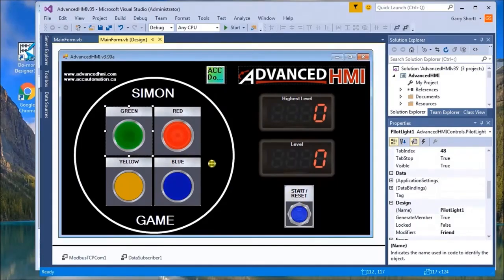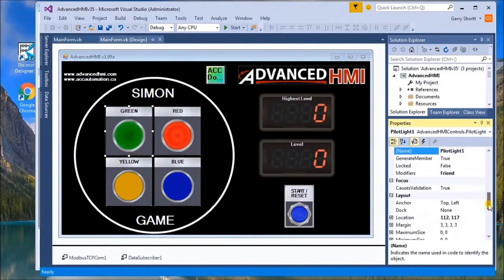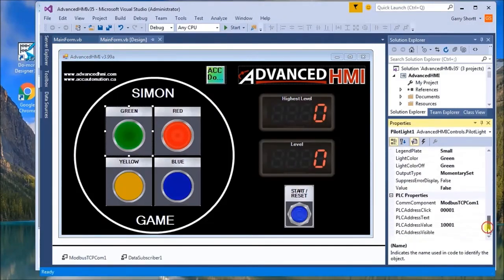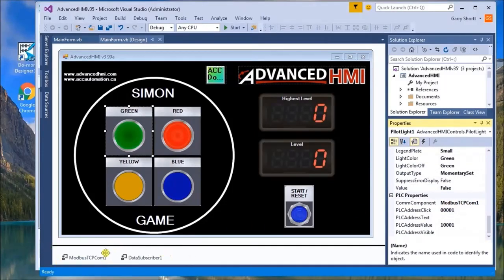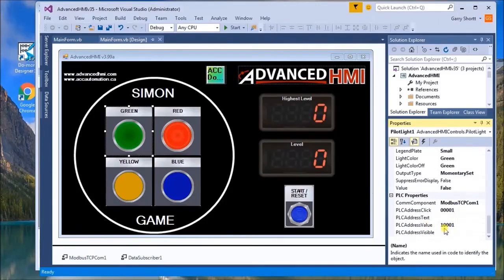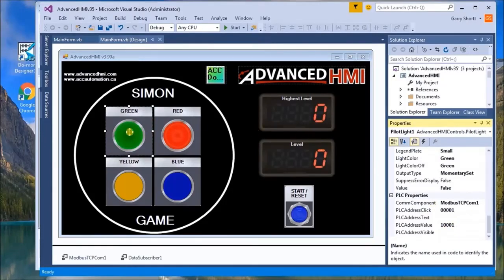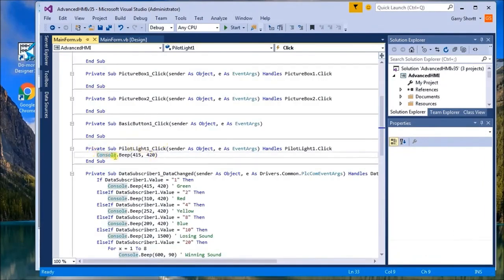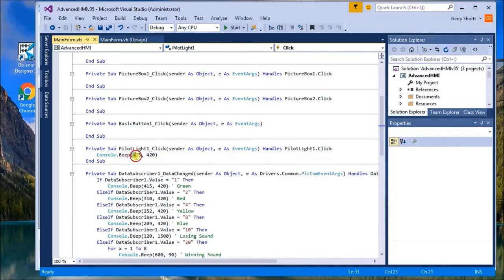If we look at each individual color like our green, it's a pilot light and here we set our Modbus communication which is same as here. We have our address which is one and we have our value that we're actually sending back to the PLC which is address 1-0-0-0-1. If I actually click on the green itself, which the operator would do, you can see here the console actually beeps and that's how we get the sounds.